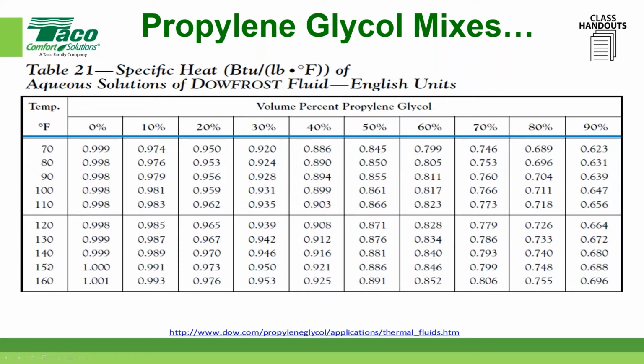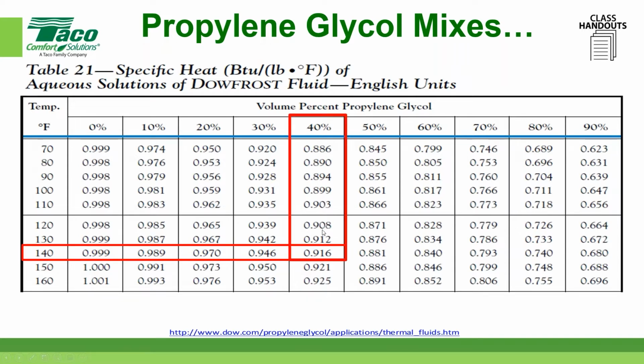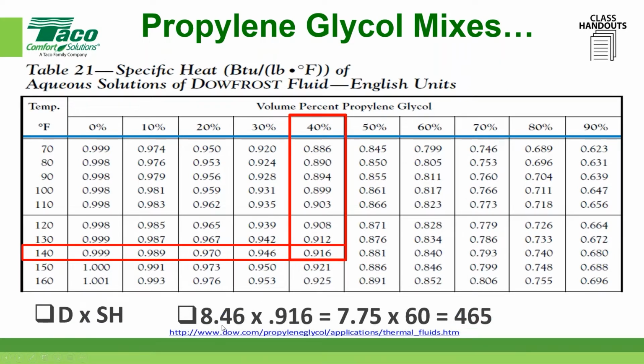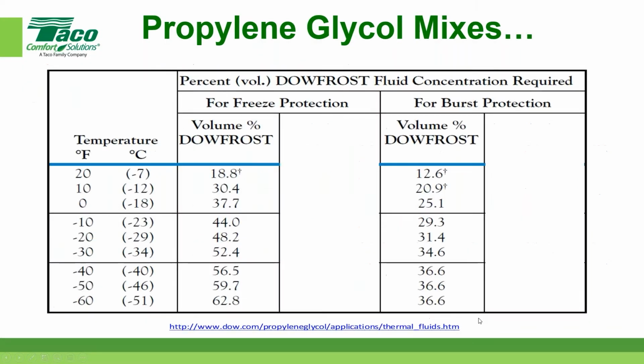So let's use the same for consistency's sake, 140, and over here at 40%. And this number here, what do we do with that? Well, that's an actual deduct, okay? We take that 8.46 from the previous slide, and we get a deduct of almost 10%. That puts us back at 7.75 times 60 minutes in an hour. That's why 40% propylene glycol at 140 degrees, we'd use a constant of 465. Everybody okay with that?